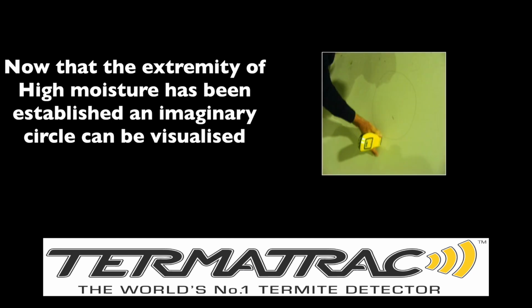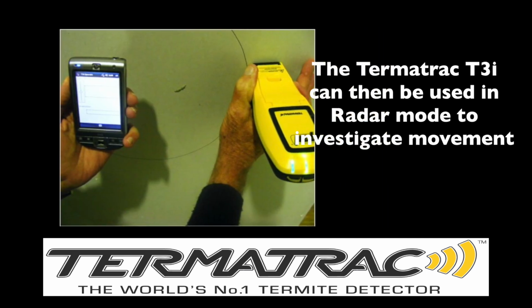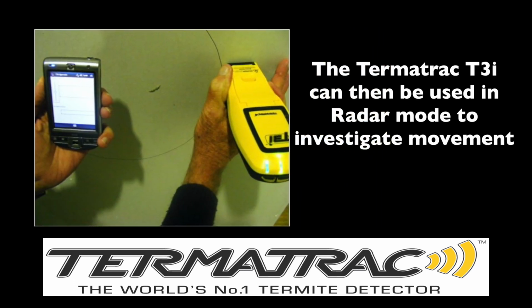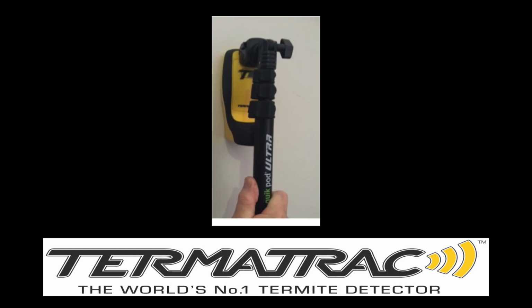What you'll have is an area of extremities of high moisture. This could be in any particular shape you've drawn out. You then click over to the radar sensor and move in between and around this area that you've now marked to investigate any motion that may or may not be in there. Any air gap between the T3i unit and the material being tested may alter the values being shown.